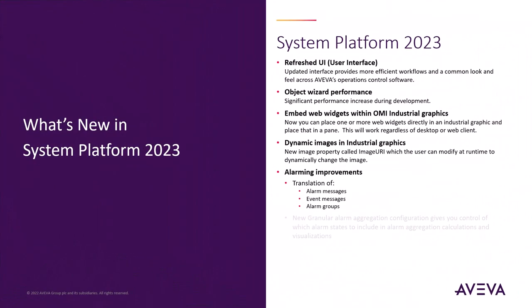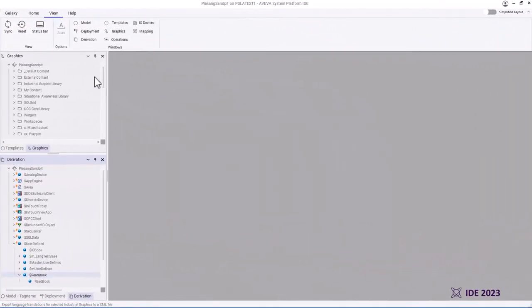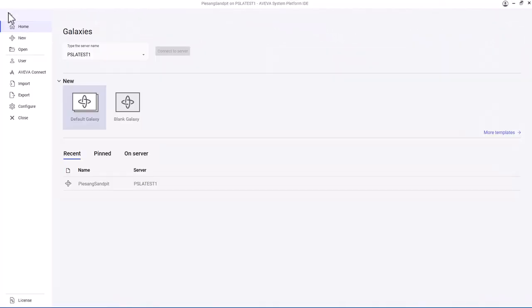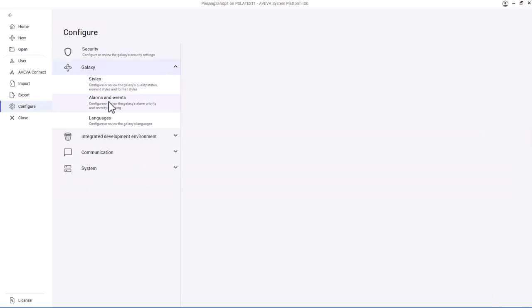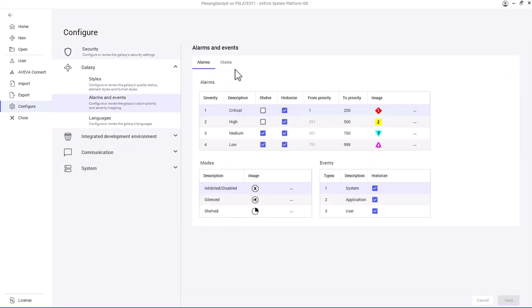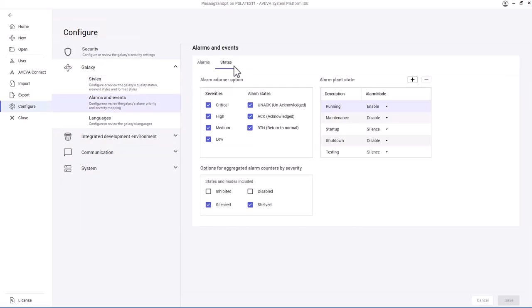We also improved the granularity of alarm aggregation configuration. One of the other great features of System Platform is the ability to keep track of alarms. In System Platform, we can aggregate alarms across the hierarchy, and by default in previous versions, those aggregations included alarms in certain states, specifically the silenced and shelved state. What we've added in 2023 is the ability to pick which of these states should be included in the alarm aggregation. Users can choose from a combination of inhibited, disabled, silenced, and or shelved alarms.